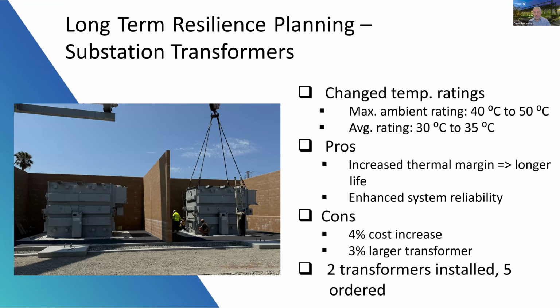As a result, BWP changed its temperature ratings for its substation transformers. The maximum ambient rating was changed from 40 degrees Celsius to 50 degrees Celsius, and the average rating was changed from 30 degrees Celsius to 35 — that's the average 24-hour, daily rating.